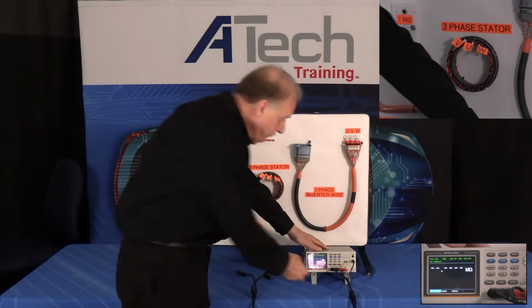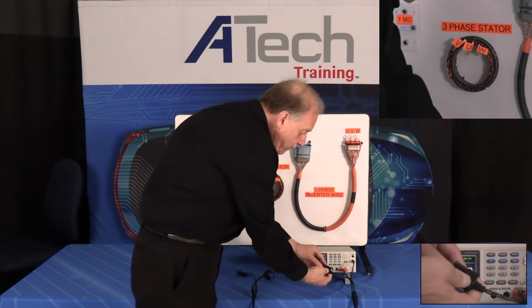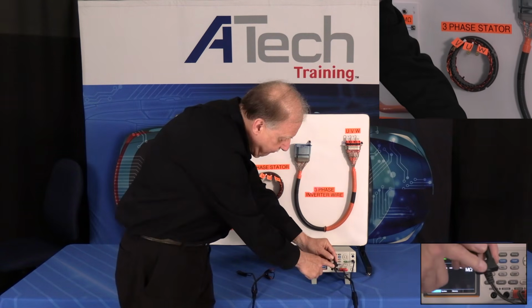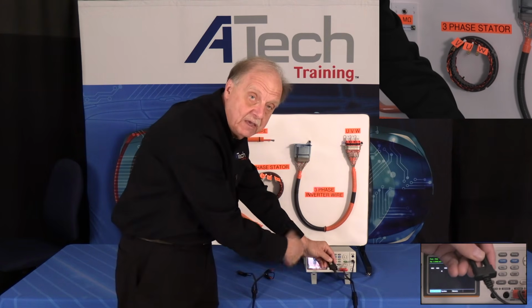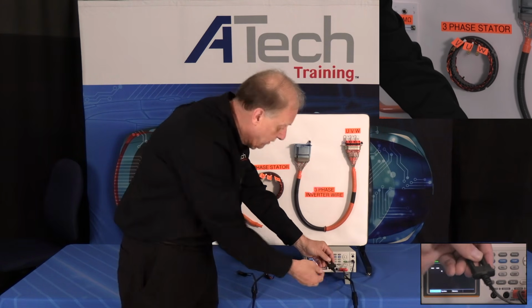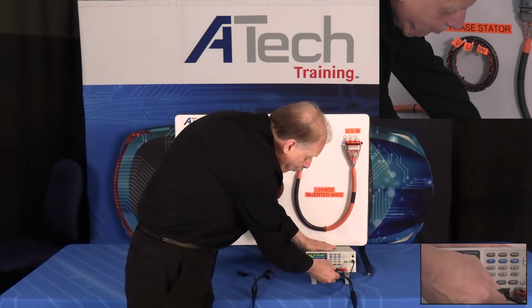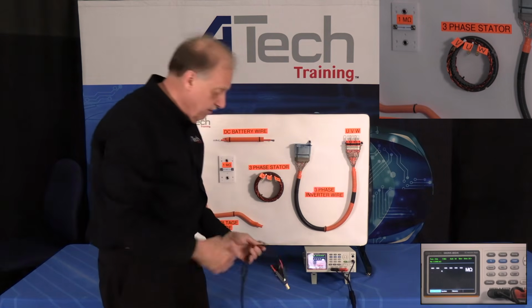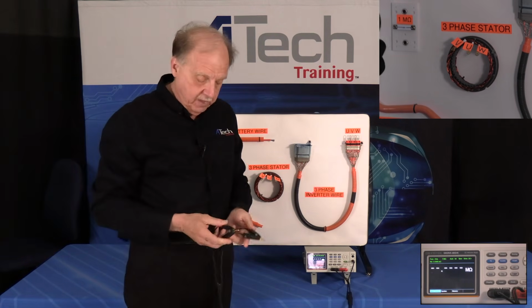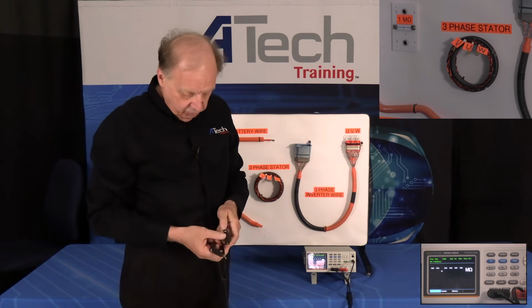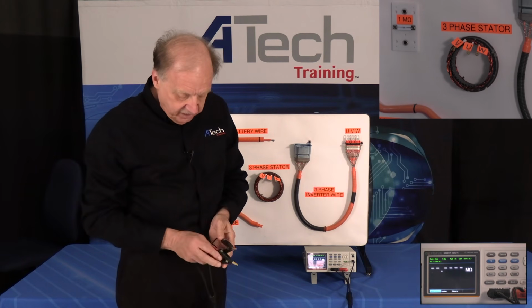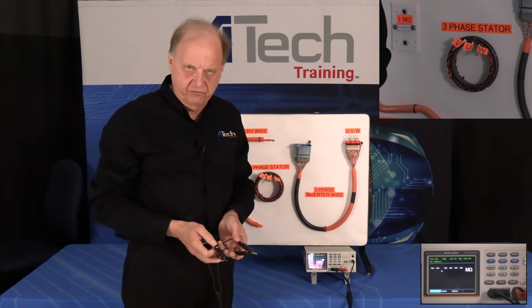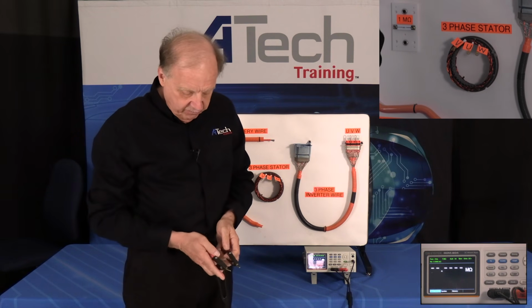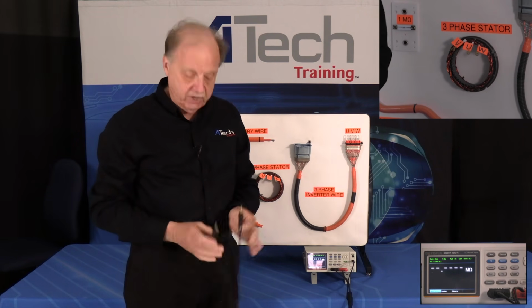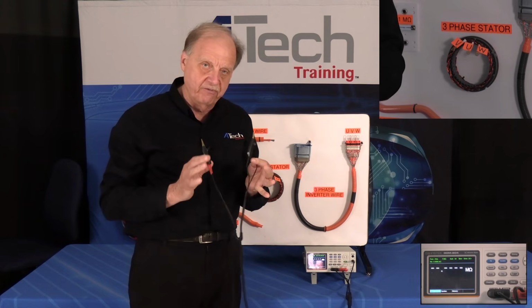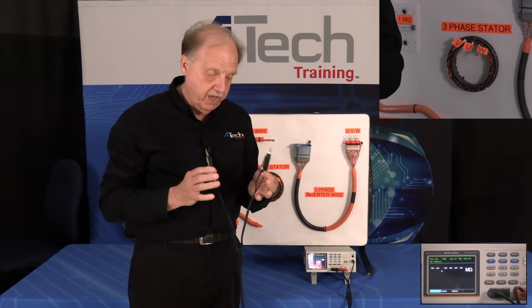First, look at your meter. One side says sensor, and the other side has nothing marked on this particular one, so make sure you plug it in correctly. Also look at our leads, which are a little different. One side of the lead is blank, that's the current side. The other side is the sensor side, so you have to check it. Notice we have 4 wires instead of the normal 2 we'd have with standard leads.